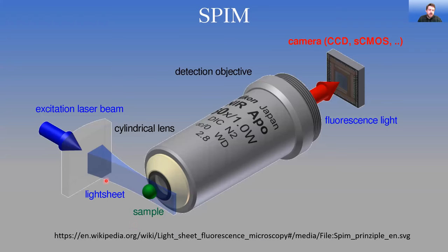So for those of you that aren't yet aware of what selective plane illumination microscopy is about, it's a relatively new mode of fluorescence microscopy where, instead of using scanning optics, you use a sheet of light that's passed into the sample parallel to the focal plane of a detection lens. This has the ability to create 3D data by optical sectioning, similar to what you'd get with a confocal. But instead of passing a laser beam one pixel at a time, it's creating a sheet of fluorescence, and all of that passes directly to a camera.